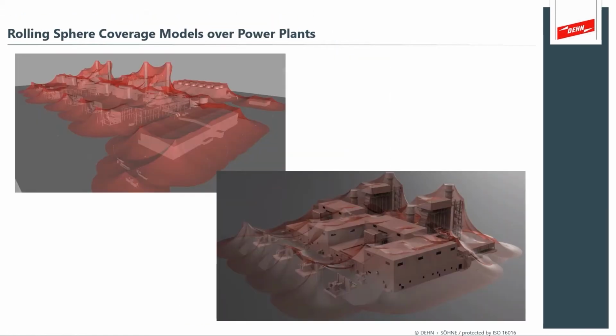So this is a really nice set of illustrations showing those coverage models over these complex structures at such a power generation plant. And you have a really nice rendering showing the air termination rods over the structures, like the heat recovery systems, where the electric generators are inside these buildings. So these are all delicate structures, and especially the highly exposed high voltage step-up transformers that feed the actual power grid. So in illustrations like this, you get a really good feeling for the coverage model calculation and the coverage you can achieve from your air terminal placement.